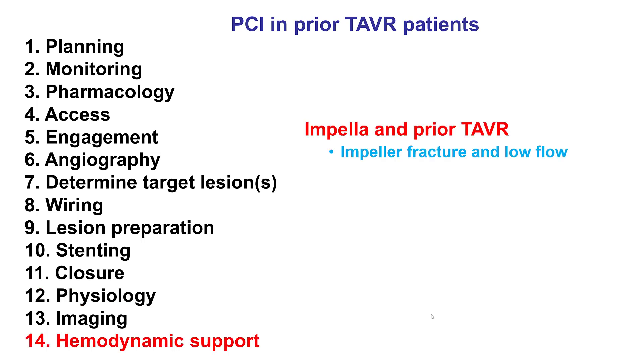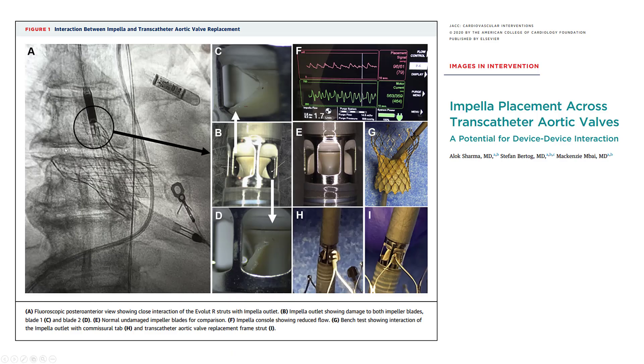Finishing up with hemodynamic support: there is a word of caution if an Impella is used in patients who have previous TAVRs, specifically with the Evolut valve, because the struts of the frame may actually interfere with the impeller and lead to fracture of the impeller blades. That can lead to low flow as well as embolization. So Impellas should be used with caution, or not used, in patients who have TAVR — especially with the Evolut CoreValve.